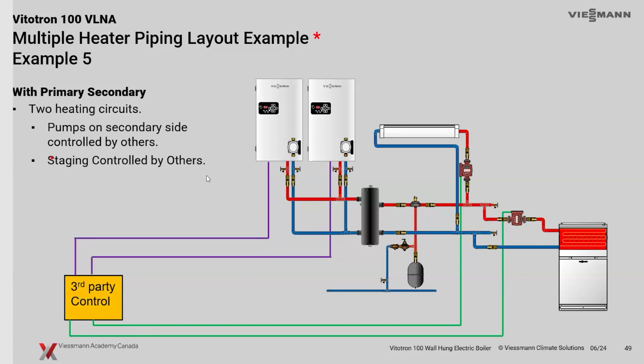As I mentioned, in some applications, we're actually seeing guys install the boilers at the manifold locations for their different loads. So they're wiring their connections in separate areas. So the boilers are in completely separate areas of the buildings. But if you have a central plant here and one boiler is not enough, it is possible, obviously, to add boilers, and we call that cascading.